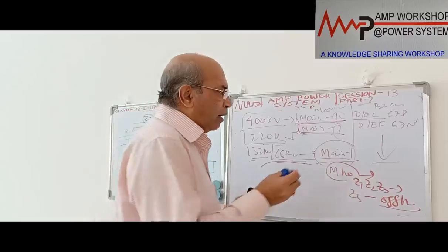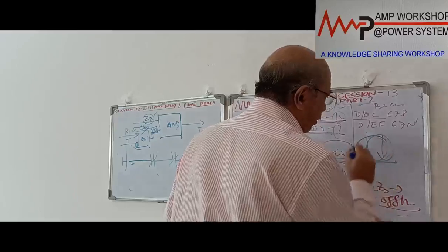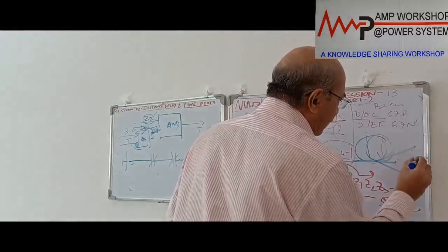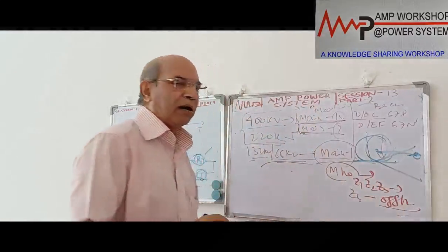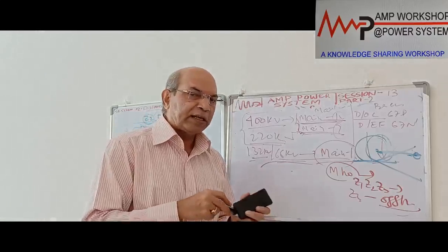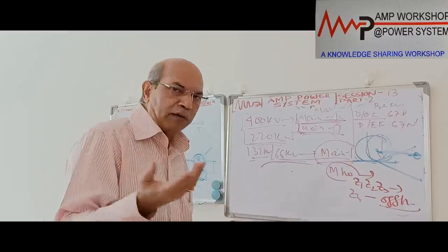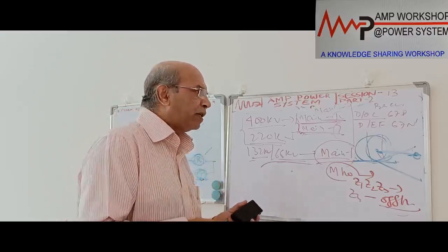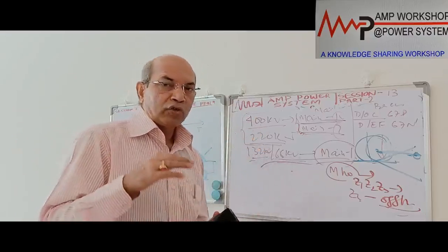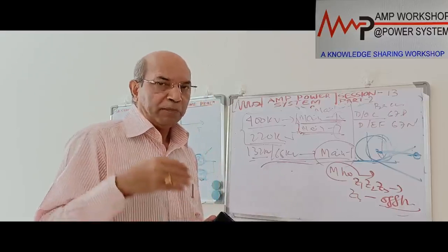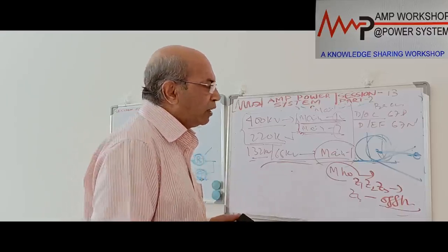During power swing, when we draw the load diagram with our loading angle, the impedance can come inside the relay characteristics. In that case the relay will operate. So a power swing blocker will be there, then a switch-on-to-fault blocker should also be present in the relay. Then all the relays operate on the VT supply, so in the case of VT supply failure or VT fuse failure, a failure monitoring scheme should be present with the relay. That is also required.